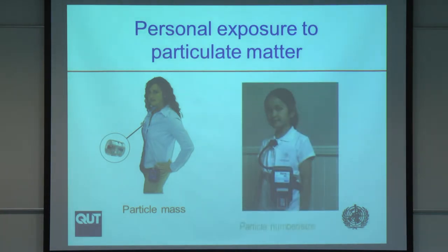Now this is the next step from this, and here is a device called the NanoTracer, which measures particle number concentration, and we are going here to the very small sizes, basically from about 5 nanometers to about 200 nanometers. So as you can see, this measures personal exposure, does it in real time, and gives 1 second resolution, depending on what mode we set. In either case, it is possible now, but obviously you are still wearing a bulky device attached to you, which presents some complexities. I'll later on come back to the results of this kind of monitoring.